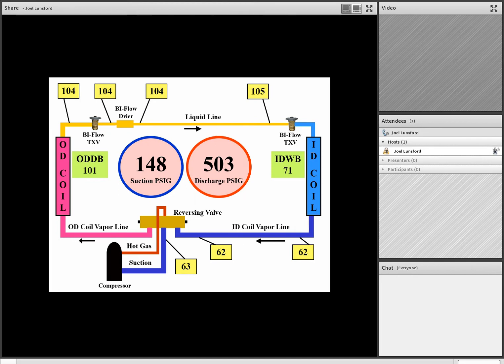Now remember, team, in the cooling mode of operation, the outdoor coil should have a subcooling level of about 10 to 15, but we have 30. So the outdoor coil is jam-packed full of liquid. The indoor coil is about normal. Suction pressure is slightly high, but not too bad, and we have high discharge pressure. So normal suction, normal superheat, high discharge pressure, high subcooling.